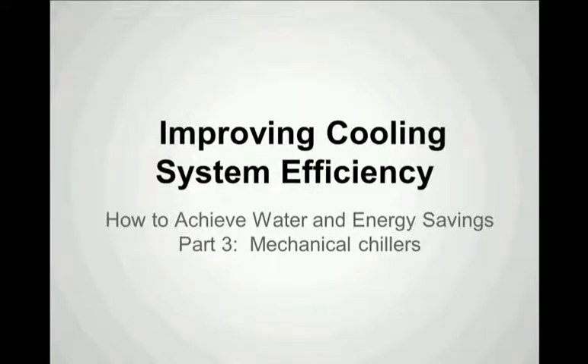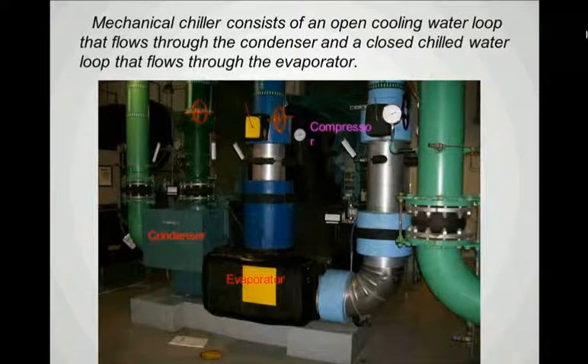Improving cooling system efficiency, Part 3, mechanical chillers. A mechanical chiller is used to remove heat from the building. It's the mechanical device that removes the heat and maintains the temperature and humidity within the building at a given set point. As shown in this photograph, the mechanical chiller consists of an open cooling water loop that flows through the condenser and through the cooling tower.